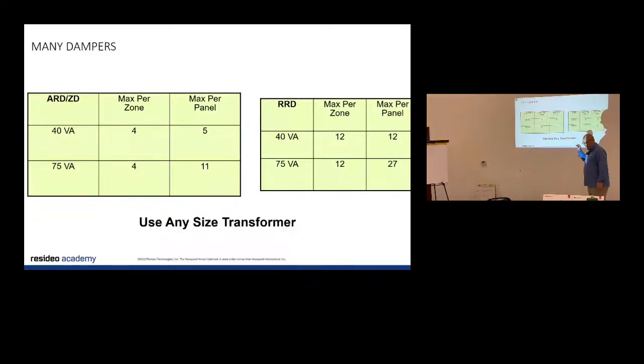The other problem is, and I get this call all the time, and I think I'm giving this to your other guys, and I can get this to whoever. If you've got a shelf with some zone panels or something on it, I would take this page and I would laminate it, because I get this call at least once a week, maybe twice a week. And it's not in the selection guide. But when I go to power, because everything in the zoning system is powered off the board, I can only power so many dampers per board because of the amp draw. If the amp draw is too high, your zone dampers aren't going to open.